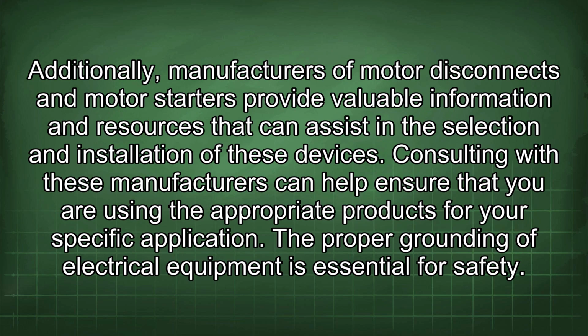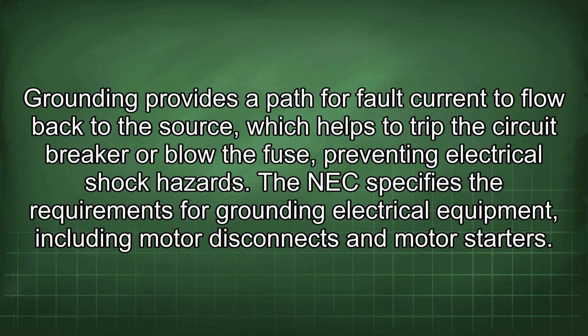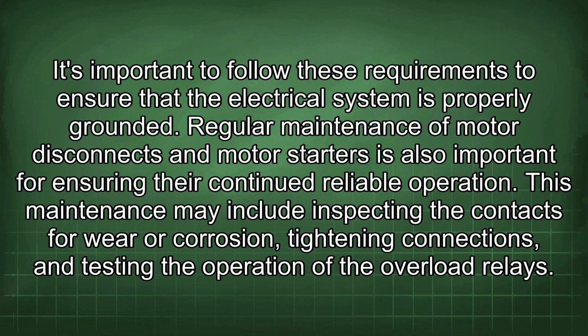The proper grounding of electrical equipment is essential for safety. Grounding provides a path for fault current to flow back to the source, which helps to trip the circuit breaker or blow the fuse, preventing electrical shock hazards. The NEC specifies the requirements for grounding electrical equipment, including motor disconnects and motor starters. It's important to follow these requirements to ensure that the electrical system is properly grounded.